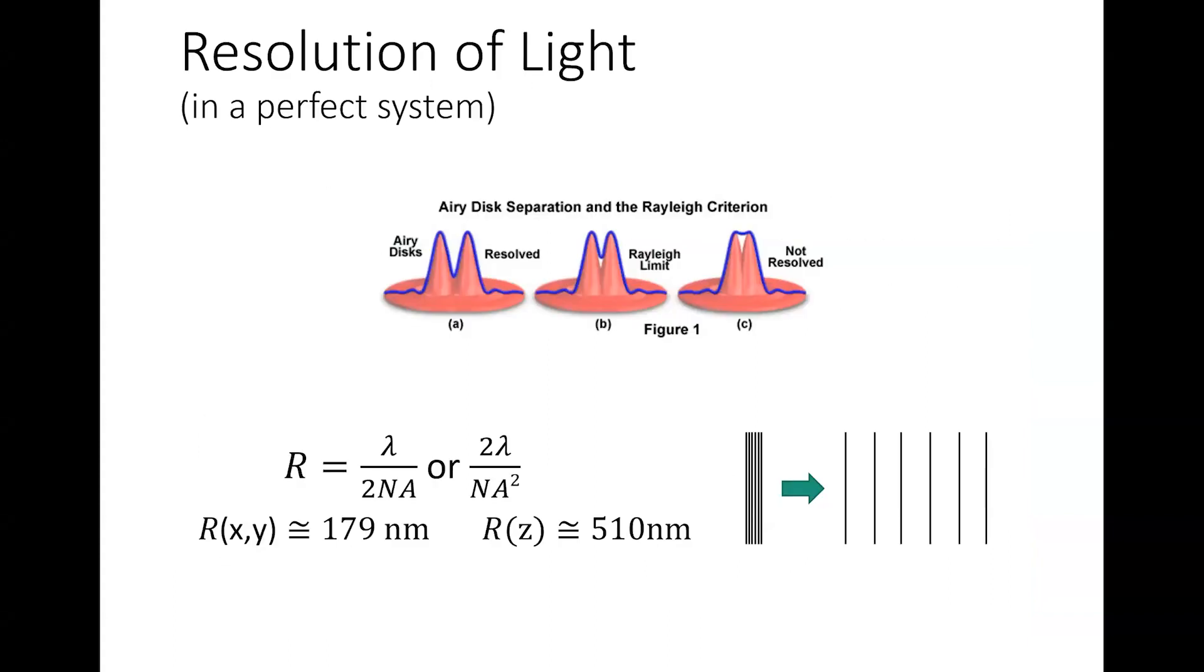The first thing to understand why we'd use expansion microscopy is the resolution of light. Resolution of light is dependent on the wavelength of the light used. In this example, we're going to use approximately 500 nanometers, which would be the emission of a GFP-like fluorophore. If we put that in for our wavelength of light divided by two times numerical aperture, we'll use a 1.4 numerical aperture objective. That would be an oil objective. This would give us a lateral resolution of approximately 179 nanometers. In our axial direction, which is always going to be more poor, we would have about 510 nanometers resolution.